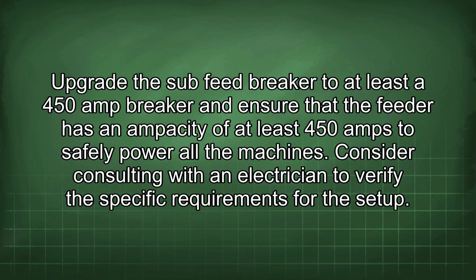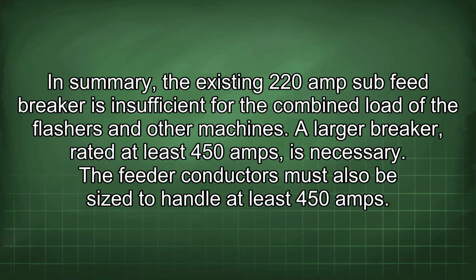Consider consulting with an electrician to verify the specific requirements for the setup. In summary, the existing 220 amp subfeed breaker is insufficient for the combined load of the flashers and other machines. A larger breaker, rated at least 450 amps, is necessary. The feeder conductors must also be sized to handle at least 450 amps.